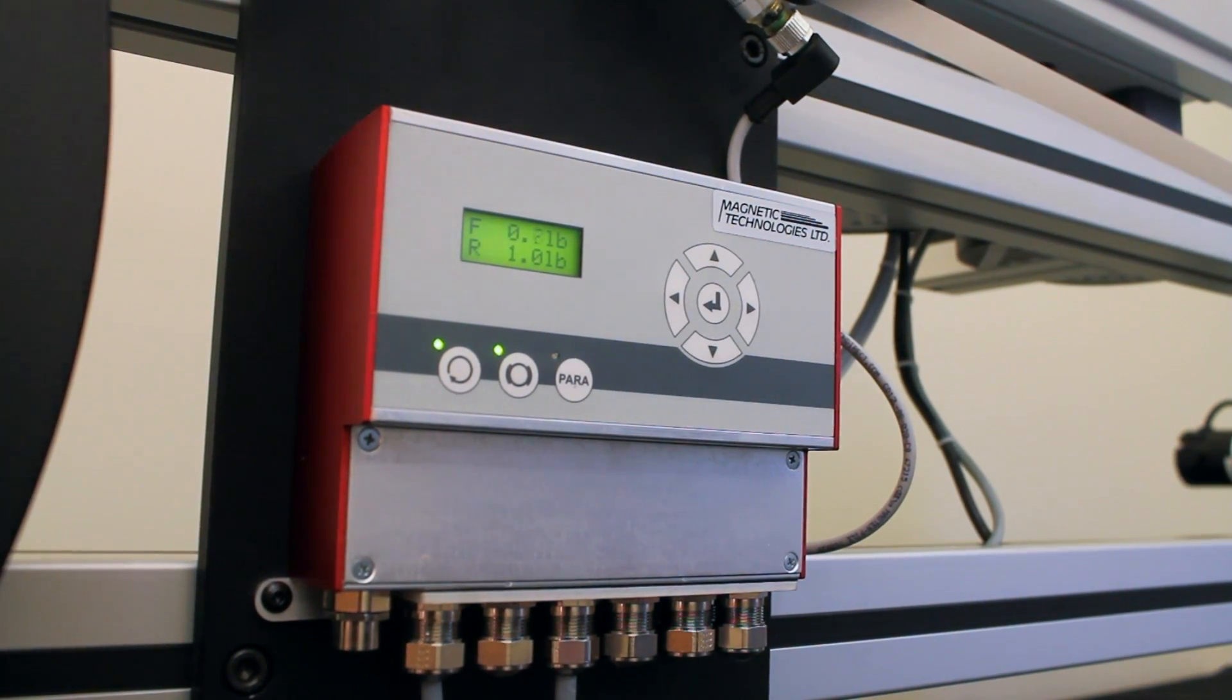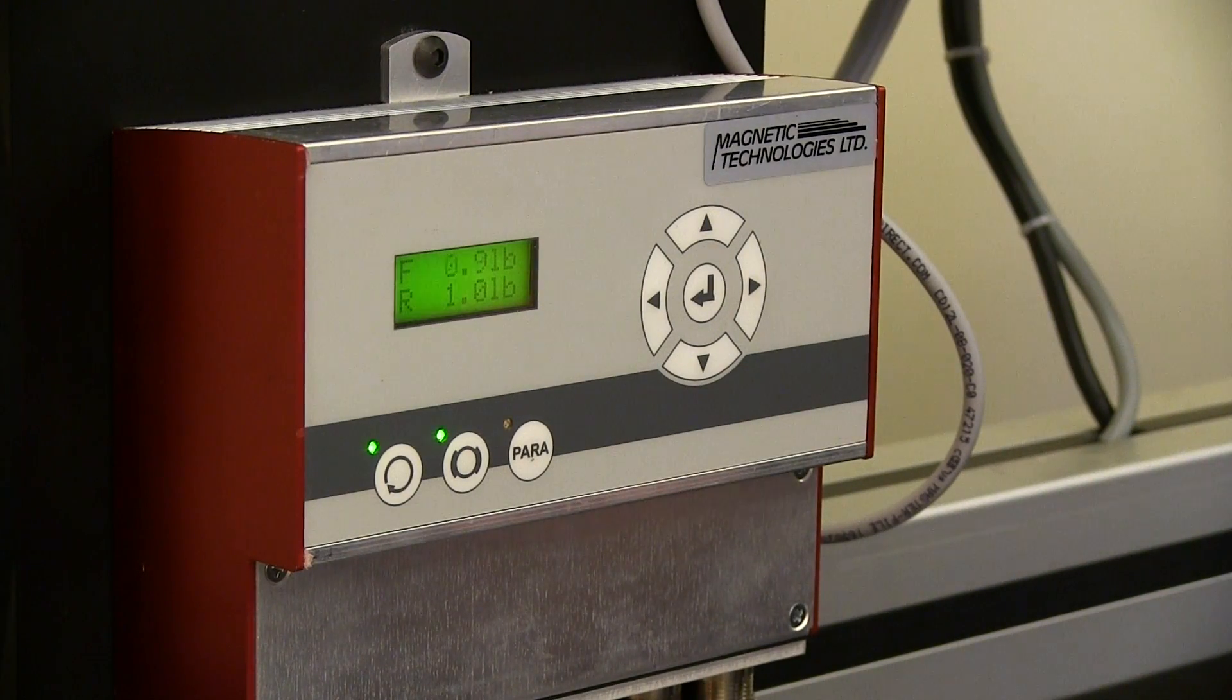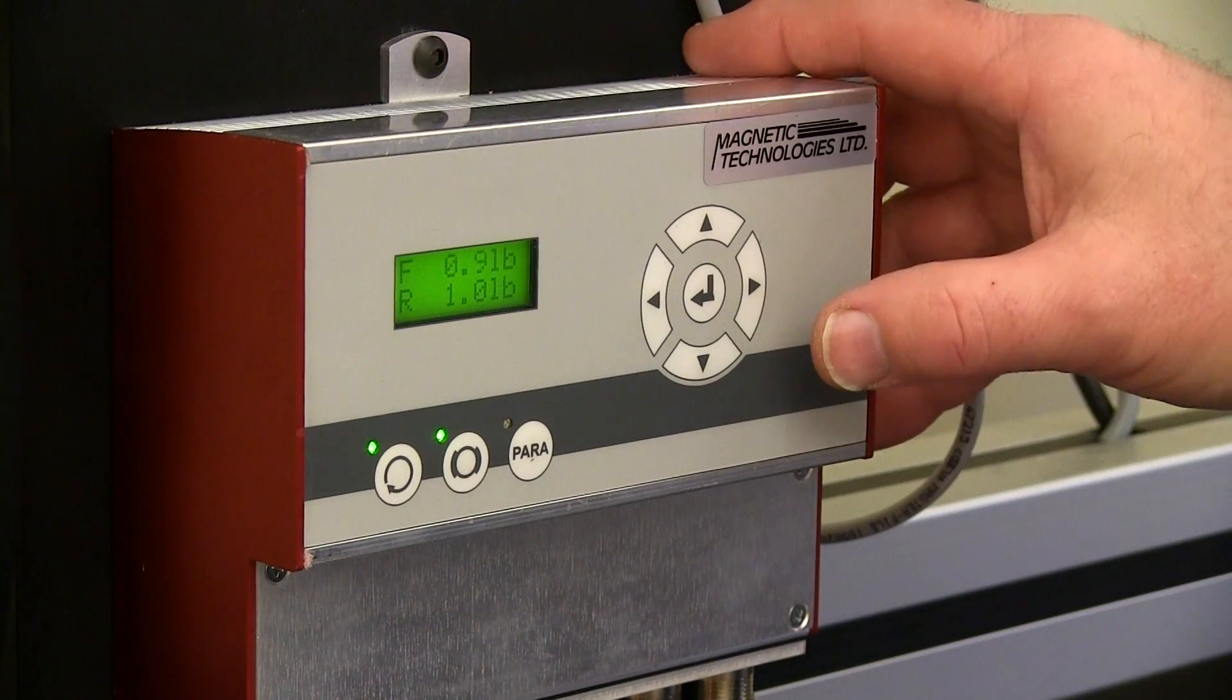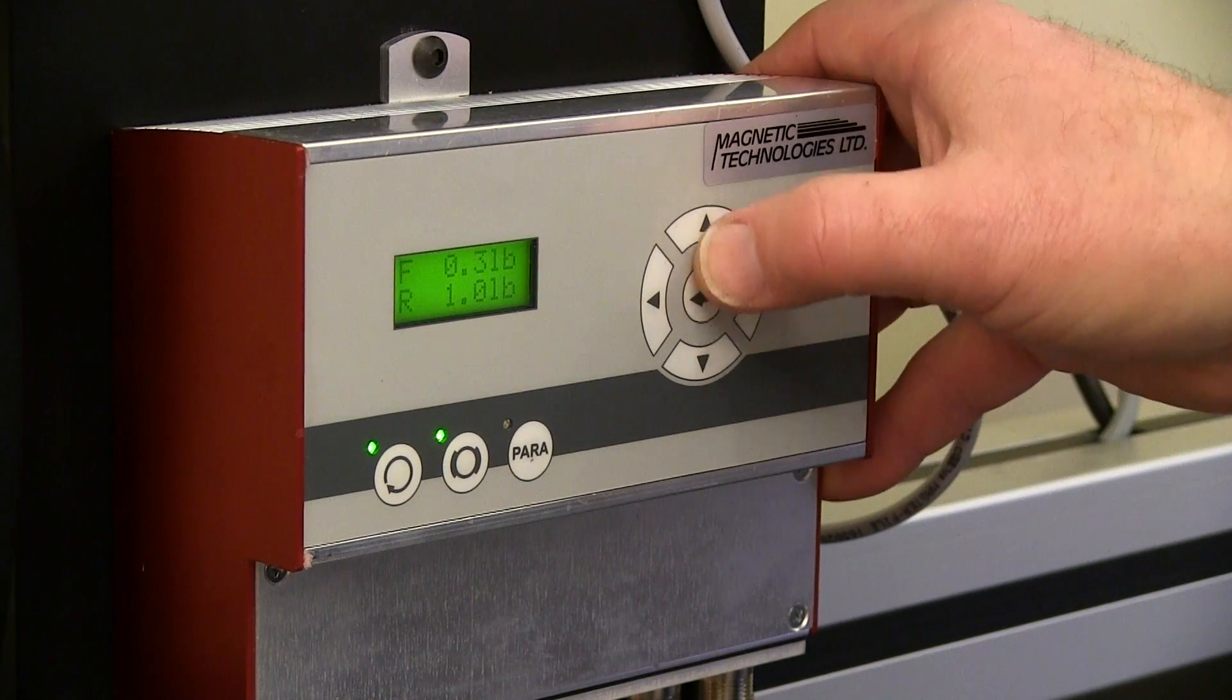In this manner, real-time, closed-loop control of tension is possible. Changes in payoff diameter as well as any variation in the material being paid off is immediately detected and torque to the brake is adjusted accordingly.